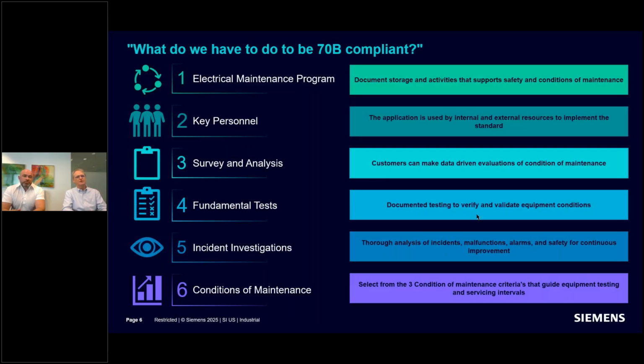Also, there were fundamental tests, things most of you are probably already doing. You may hire these out, either to the supplier or maybe a third party, to go test the breakers, for example, to confirm they actually operate as they're supposed to, that the settings in them actually work as intended. There's a lot of those that are required. And then any incidents have to be investigated. This isn't just the typical safety incidents most of you do as part of your investigations, but it could be a breaker trips, why did it trip, what were the conditions that set that, what was the root cause. That's also part of 70B. And the last part is determining the condition of maintenance.